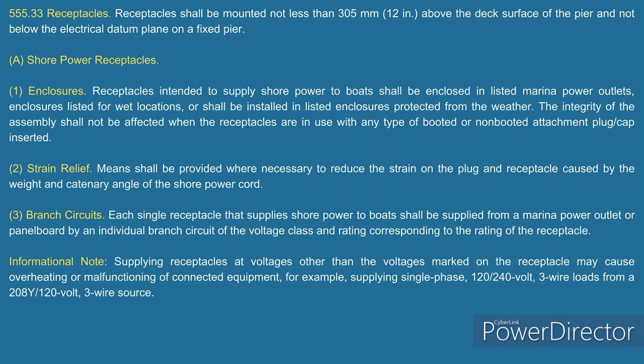And another interesting thing that I'll just tell everyone, all the viewers out there, is that the individual branch circuit, if you go look in the definition, it says it connects to utilization equipment. So technically, you start at the breaker or fuse, the final overcurrent device, and it ends at utilization equipment. Nowhere does it say it ends at an outlet.